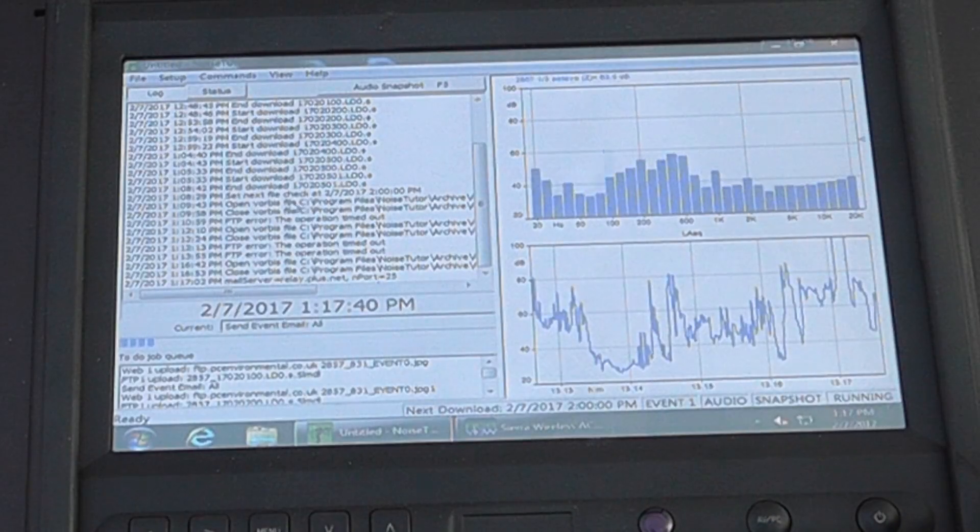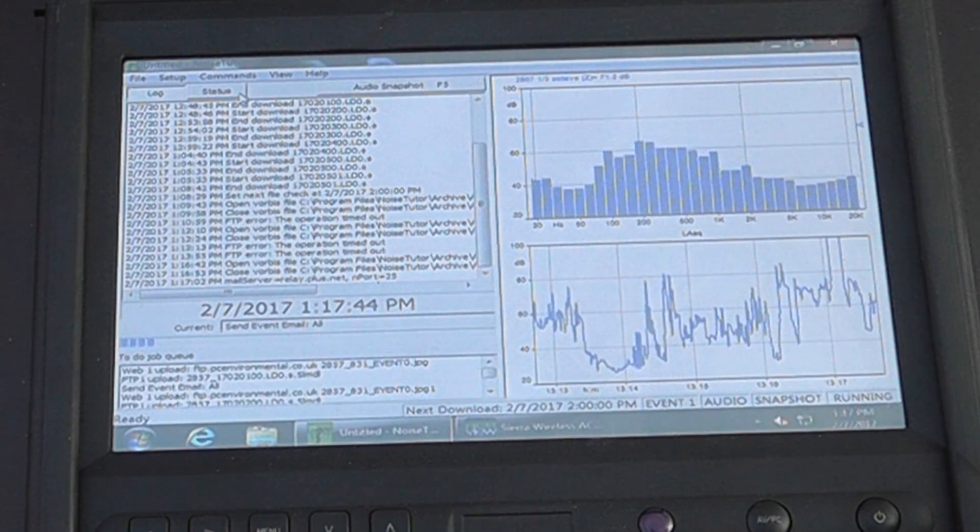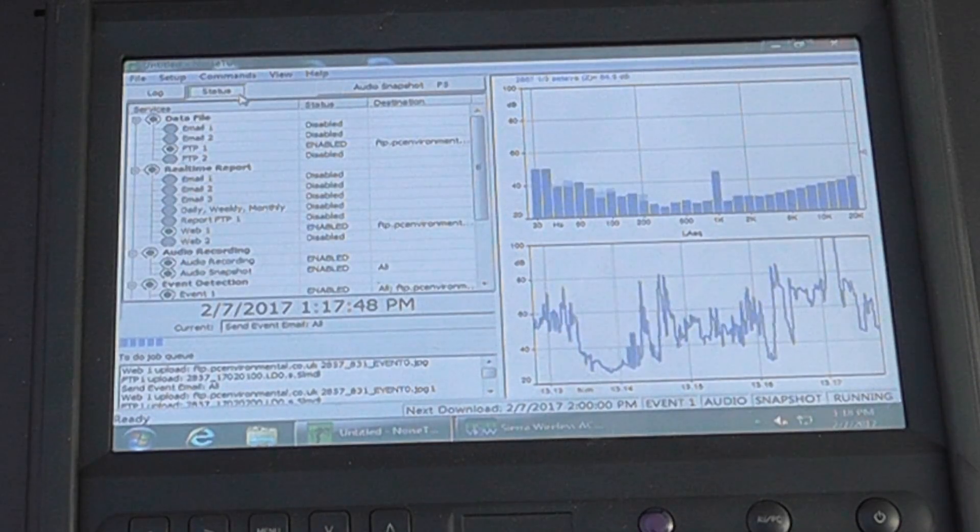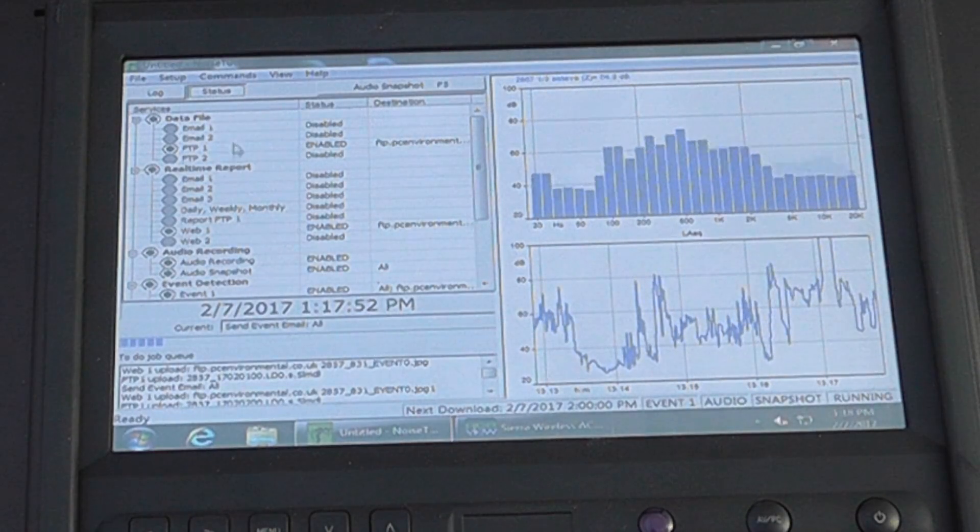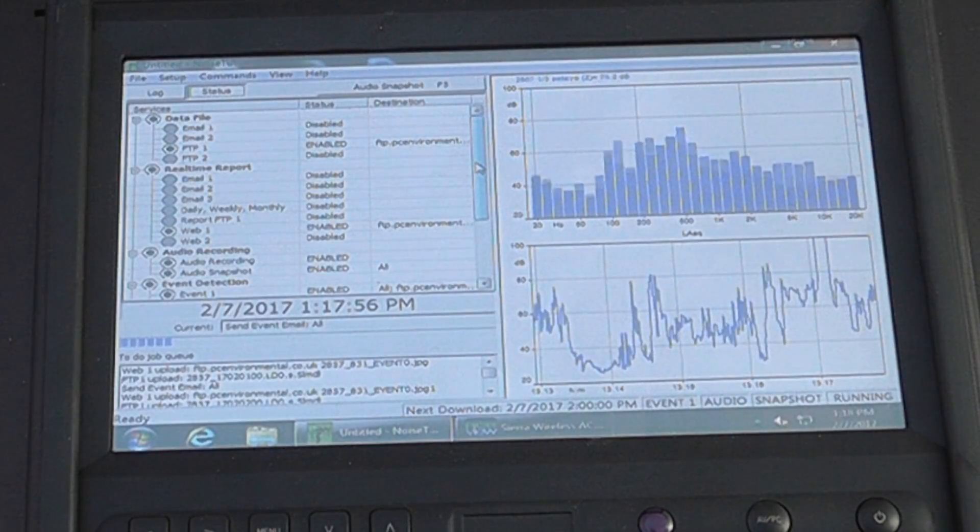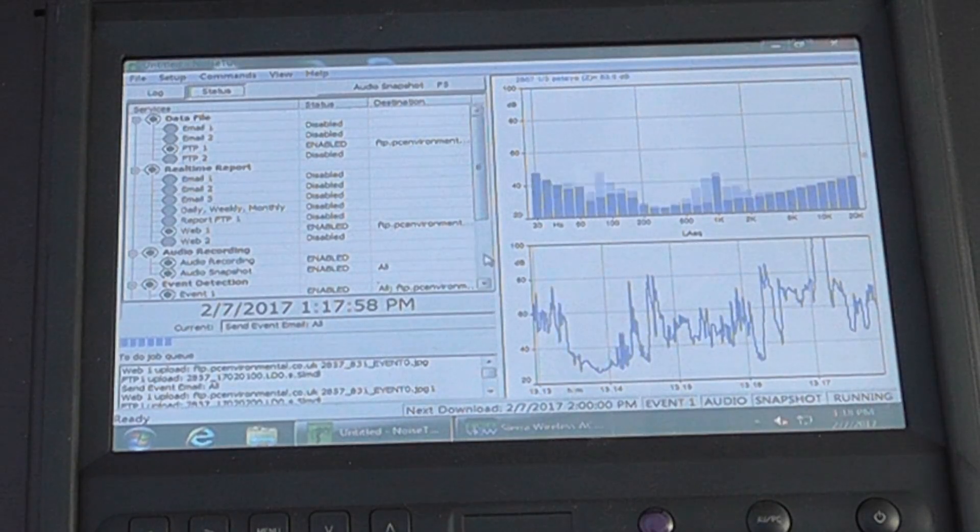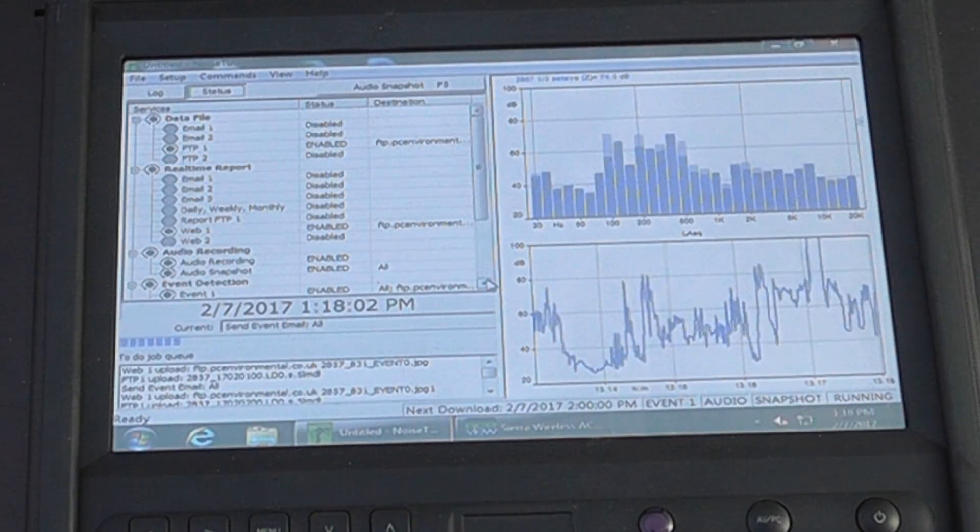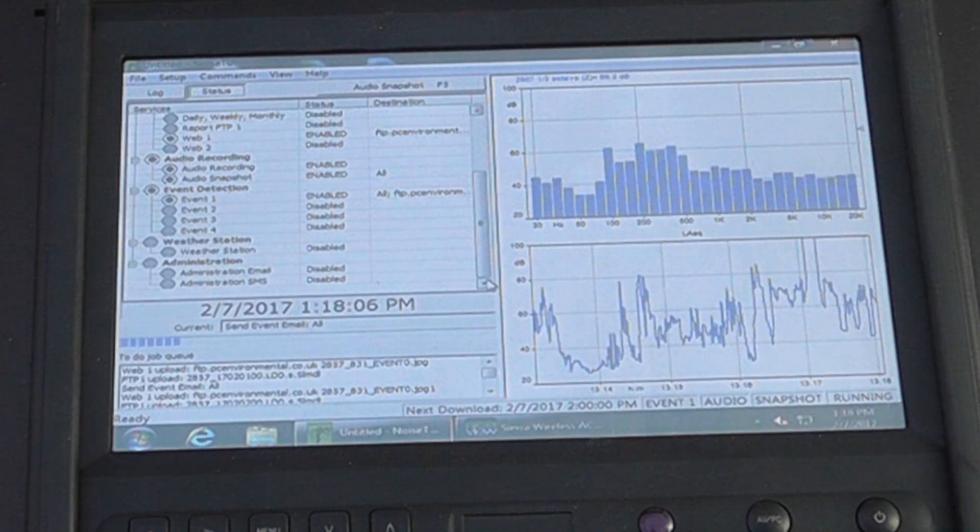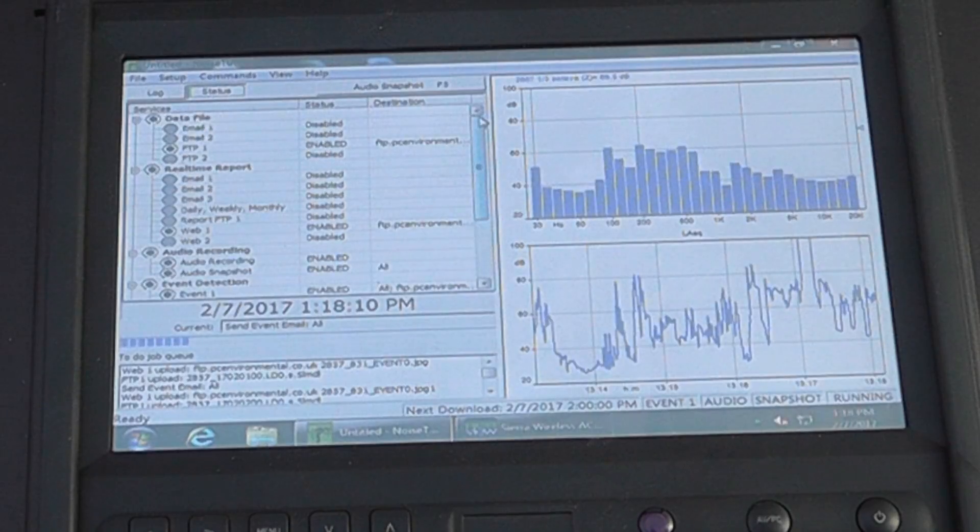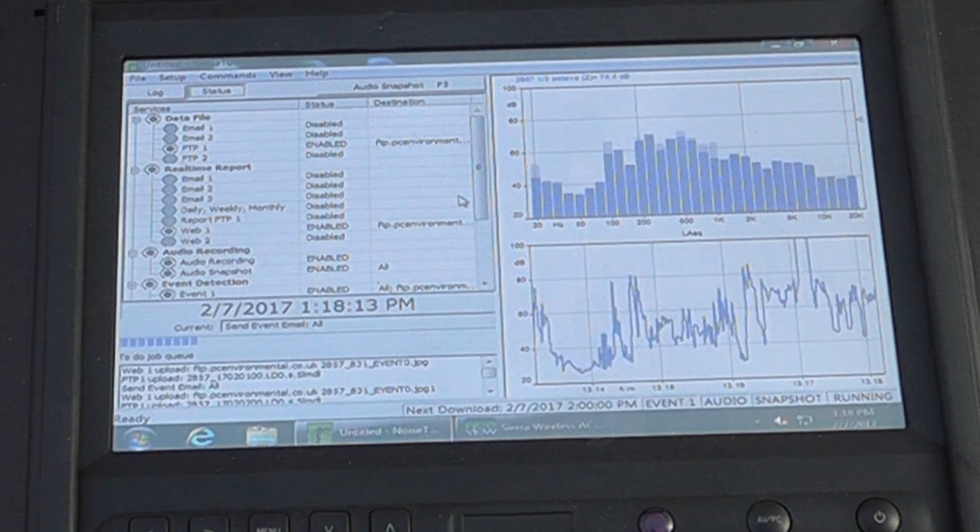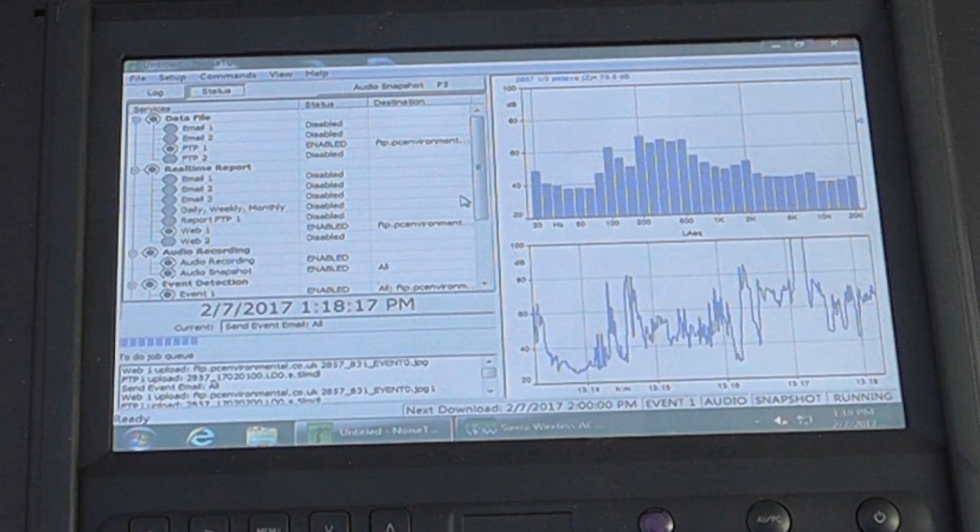We can see the status of the instrument, the full log data along with any status alerts, and what we want to happen if there are any particular issues with the device. We can configure weekly reports, event recording where data will be sent, and enable email or text message alarms via the device or review them from the remote NoiseTutor software system.